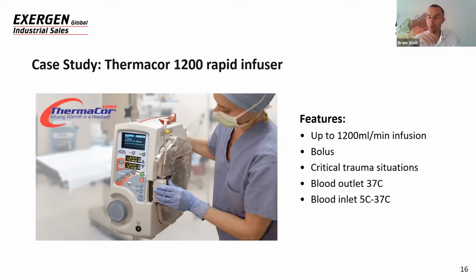However, the blood needs to be 37 degrees when it's applied, because otherwise, on top of big blood loss, you also get hypothermia. That's also very dangerous. The blood will come from donors. It's donor blood that can come from a fridge. So then it's really cold, about 5 degrees. It can already be thawed in a thawing system. Then it's maybe room temperature or already close to 37 degrees. So it can vary. But regardless of what the temperature of the incoming blood is, the output needs to be 37 degrees.